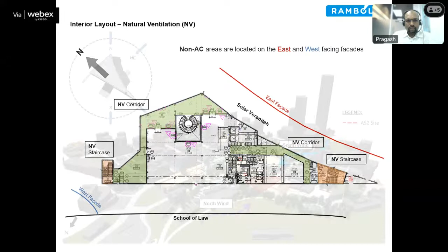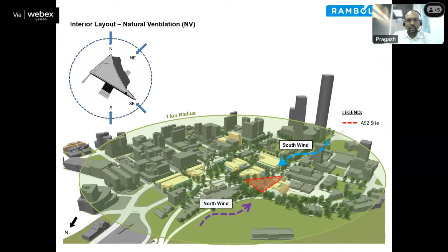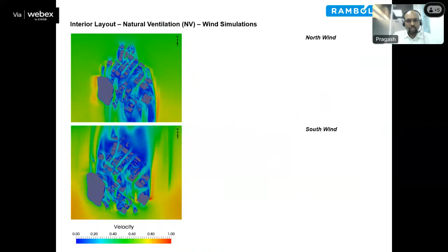For the naturally ventilated space, we have done CFD simulations, as the SMU Connexion is located in the city in Singapore, in a very dense area. We cannot just rely on the predominant wind direction. Of course, we ran the CFD simulation for a 1 kilometer radius to understand the airflow around the building, to maximize the wind flow in the naturally ventilated space, which is mainly at the ground floor and the external corridor on the other floors.